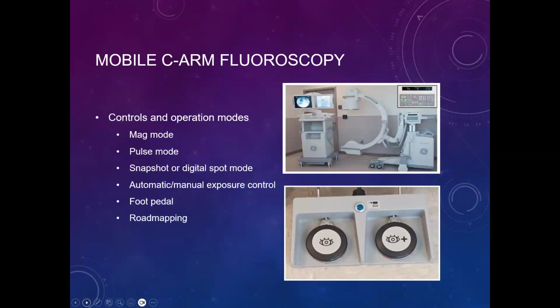These are some of the components or controls on the C-arm. You use the pulse feature to lessen the exposure to the patient. It has a normal mode, and it also has a MAG 1 and MAG 2. Of course, if you're going to magnify an image, there's going to be more radiation. You can also collimate it. There's a way to flip the image right to left and top to bottom. There is a boost on the machine, which boosts your energy. And of course, if we're going up, that's going to increase the exposure.